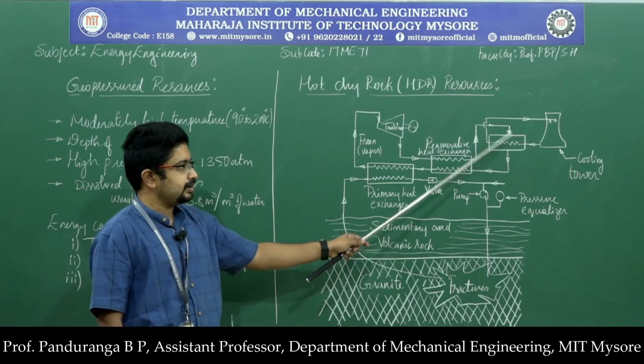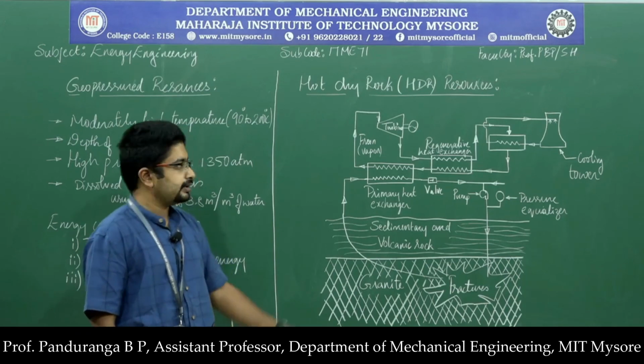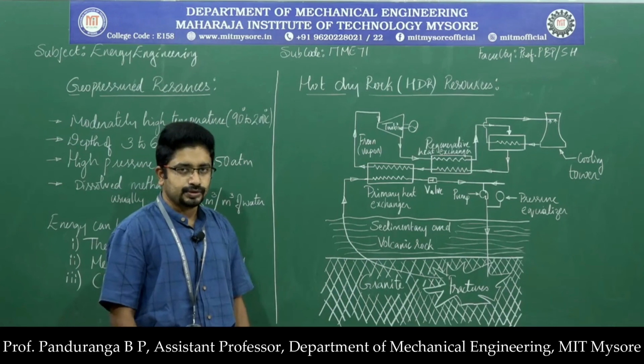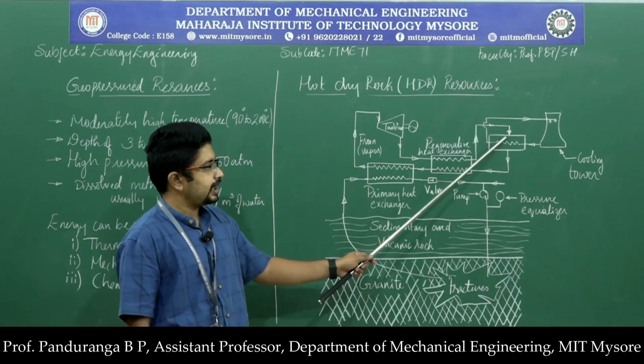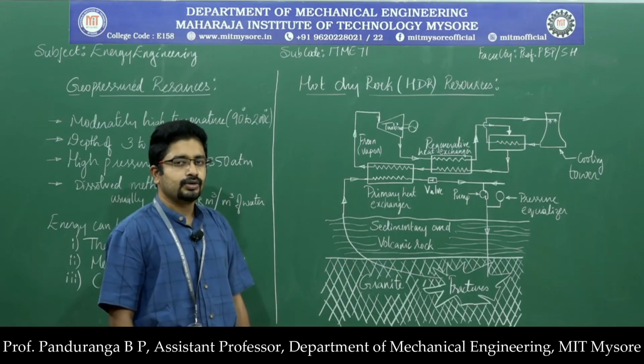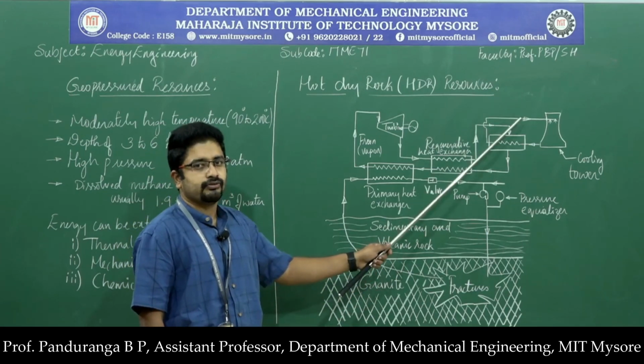In the condenser we have a closed or indirect contact condenser where the cooling water will flow inside the tubes, and the vapor and liquid mixture of Freon flows over the tubes and transfers its energy to the cooling water. So the cooling water absorbs heat energy and gets warmer.